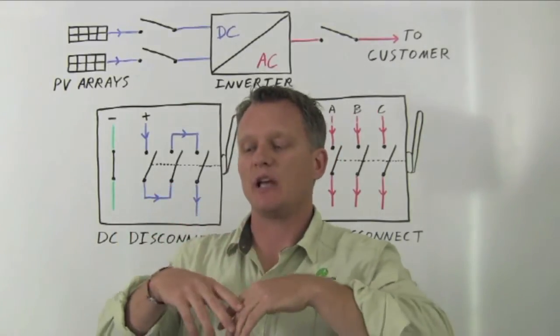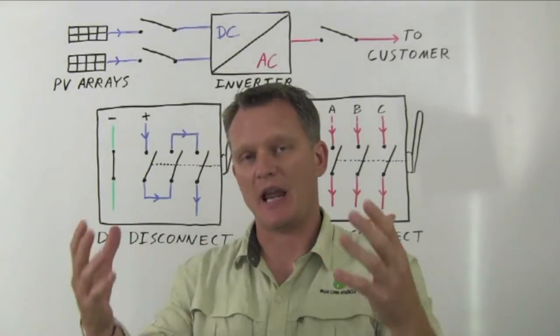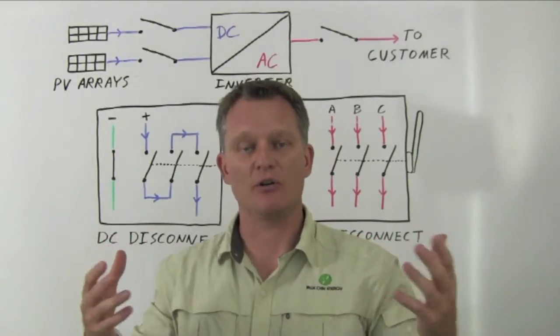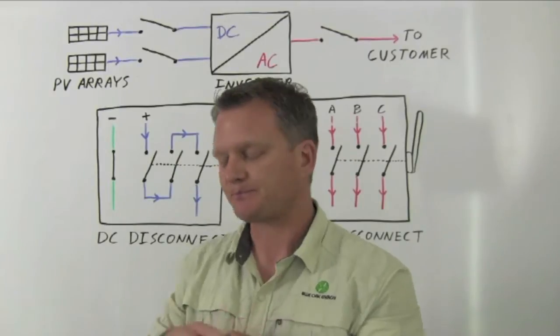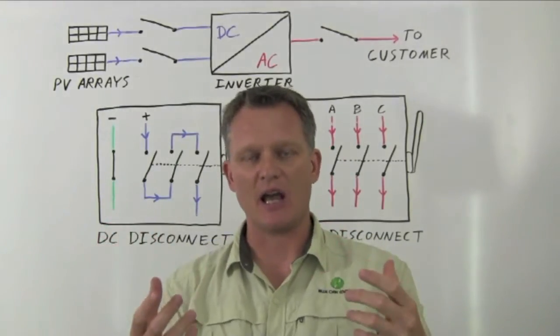And that heat, if it's not extinguished quickly, can damage components, can damage material, can actually hurt personnel. So these load break disconnect switches have to be designed in such a way where that arc extinguishes quickly.